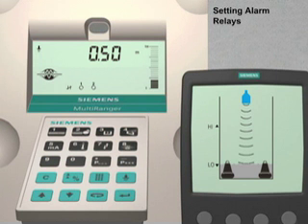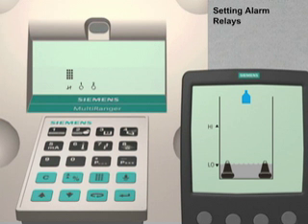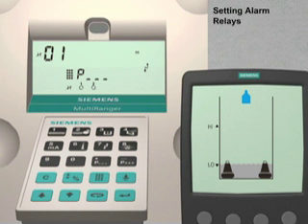To add the high and low level alarm relays to our duplex pump application, we will first put the Multiranger into program mode. We do this by pushing the mode key then the next display key twice. The LCD display will now show P dash dash dash in the parameter number field. We are now ready to configure the four parameters necessary to control our alarm relays.